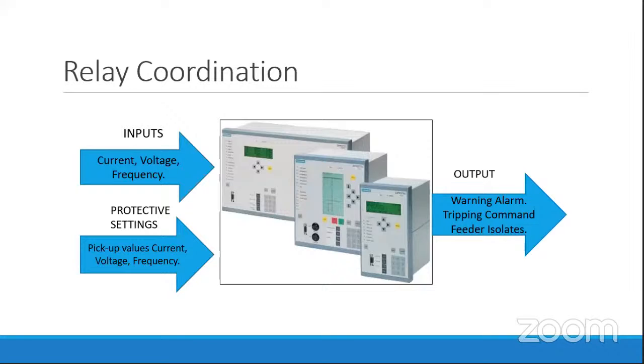Earlier, we needed separate units for electromechanical relays. If we go for electromechanical relays, we need separate compartments for separate relays. As we have studied for overcurrent protection, we need at least a minimum of two overcurrent and one earth fault relay, right? So this has been eliminated with the numerical relay. In a single numerical relay we can give protection for both the two overcurrent relays and the single earth fault relay. So these two overcurrent and single earth fault relays have been summarized in this one unit called the IED, or we can say numerical relay.